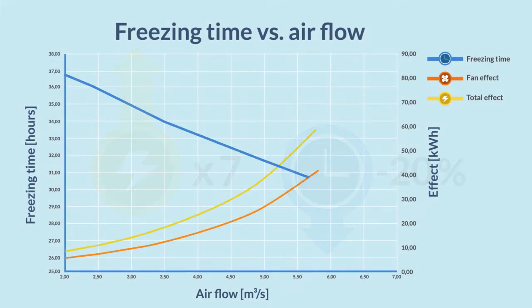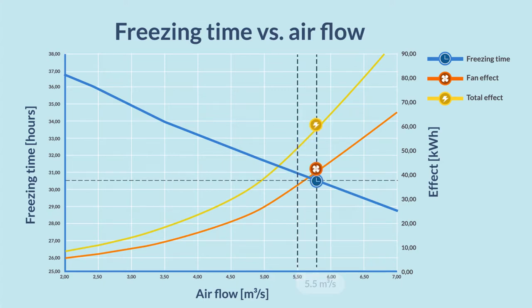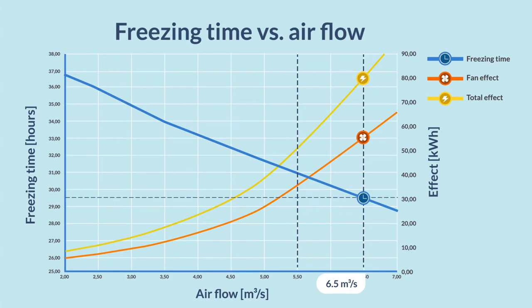Because energy consumption increases exponentially, these figures can become even more alarming when focusing on a reduction. For example, 31 hours at 5.5 cubic meters per second to 29.5 hours at 6.5 cubic meters per second. Here, the energy consumption increased by more than half, just to chop an hour and a half off the freezing time. Is this really worth it?